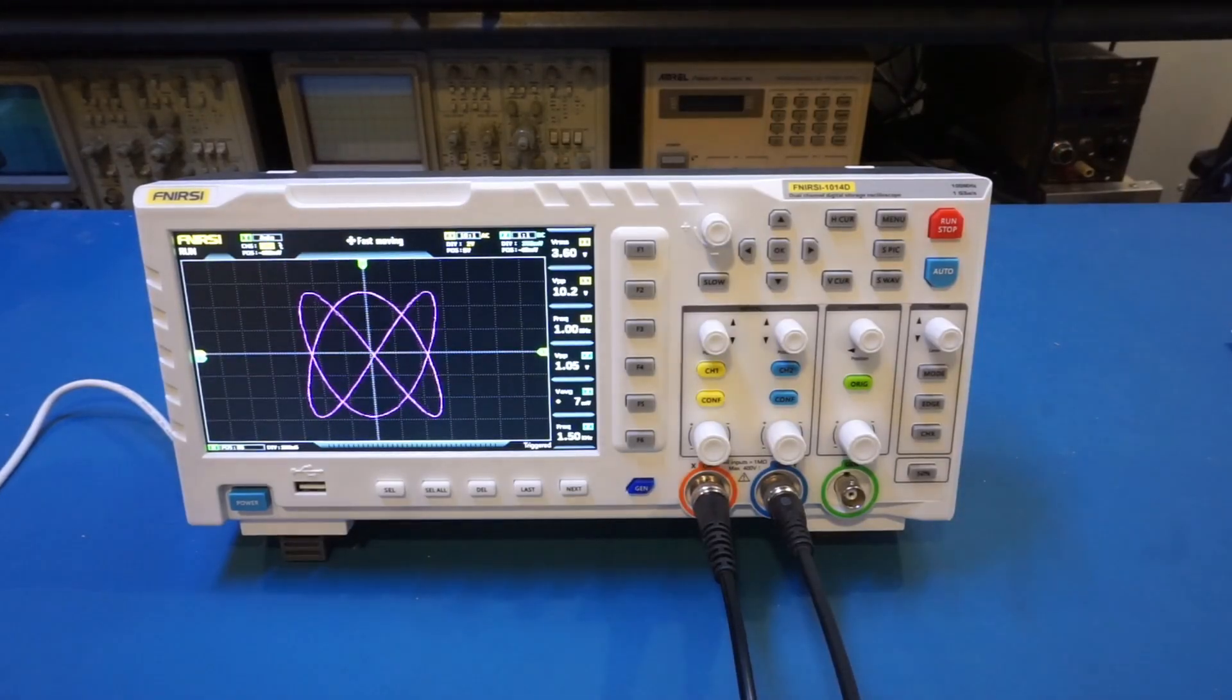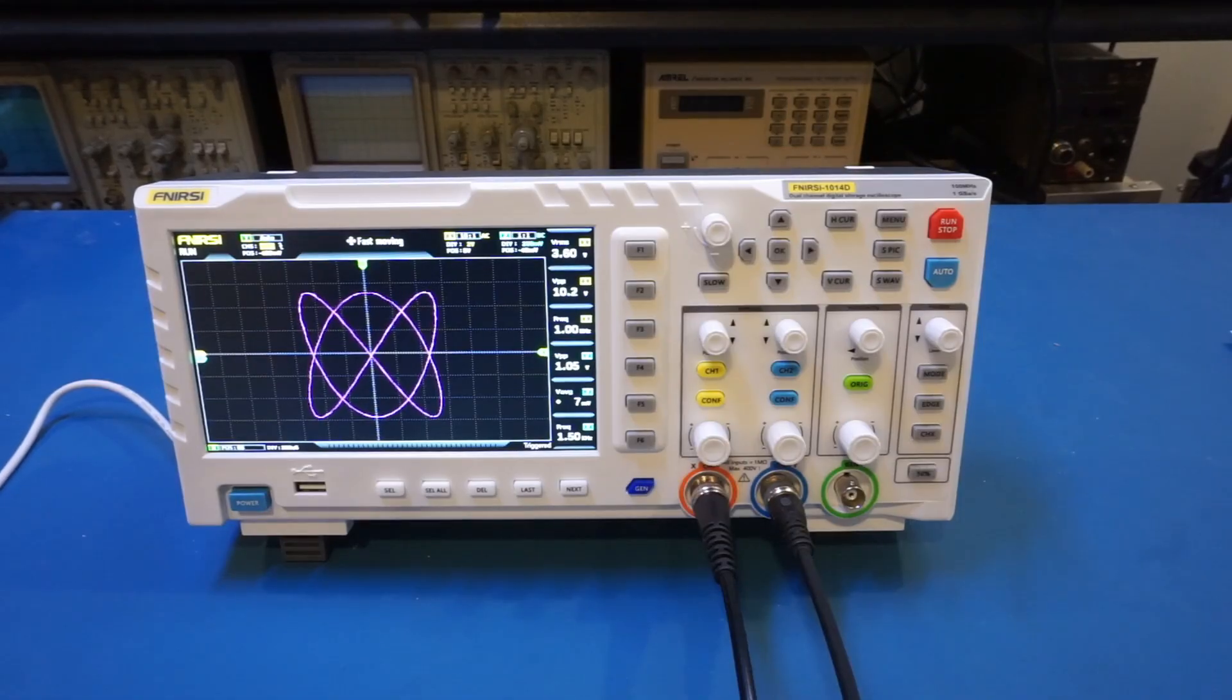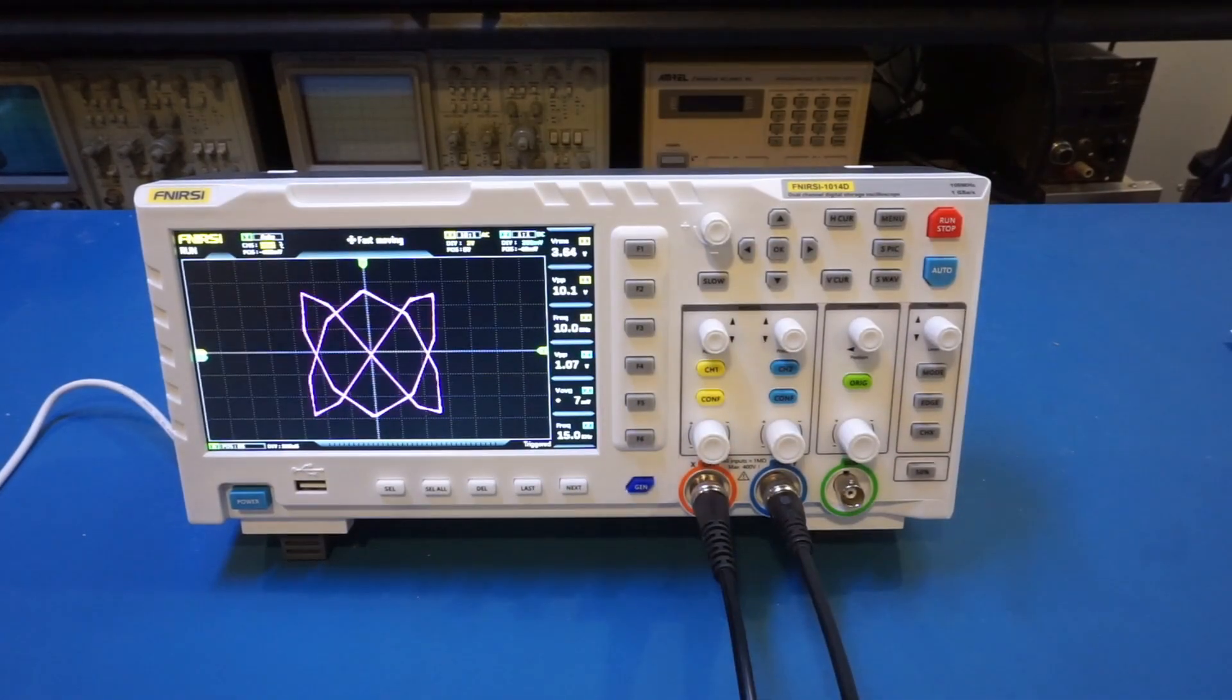And here is the scope in XY mode displaying a Lissajous figure. The acquisition rate in the XY mode is not that great. Right now I'm outputting 1 kilohertz and 1.5 kilohertz respectively for both of the channels, and you can see the figure. But if I increase the frequency a little bit more, you won't be able to see the figure anymore. For instance, right now we're at 10 kilohertz and 15 kilohertz respectively, and you can see that we already don't have enough sample points to show the figure correctly.